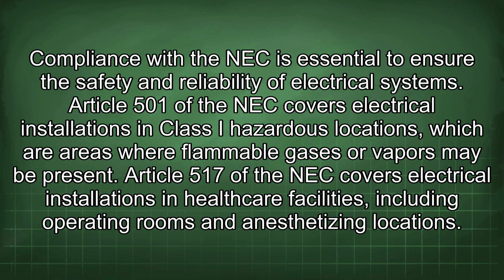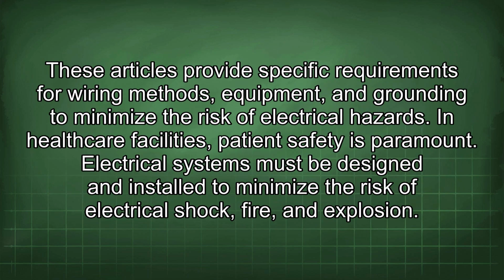Article 501 of the NEC covers electrical installations in Class I hazardous locations, which are areas where flammable gases or vapors may be present. Article 517 of the NEC covers electrical installations in healthcare facilities, including operating rooms and anesthetizing locations. These articles provide specific requirements for wiring methods, equipment, and grounding to minimize the risk of electrical hazards.